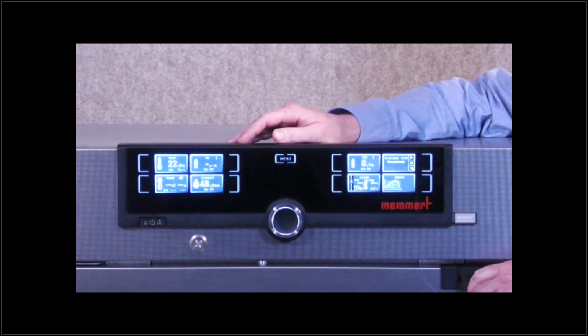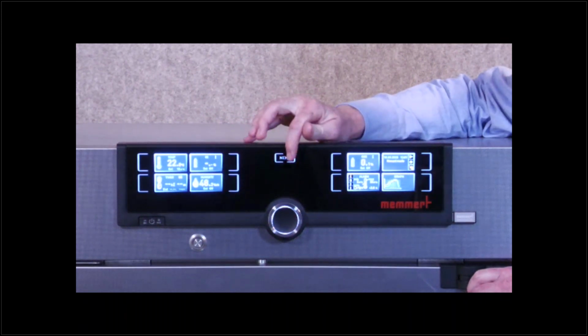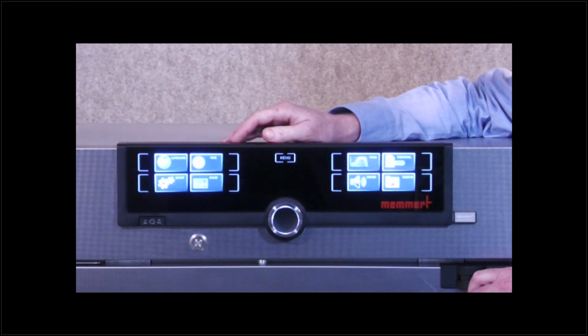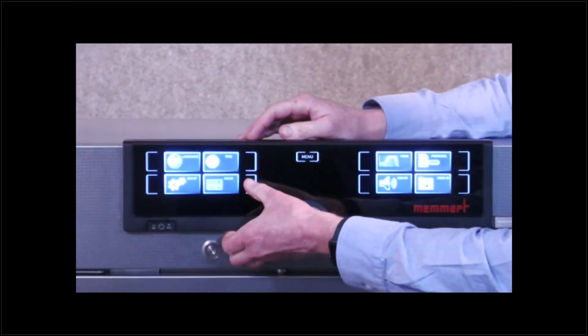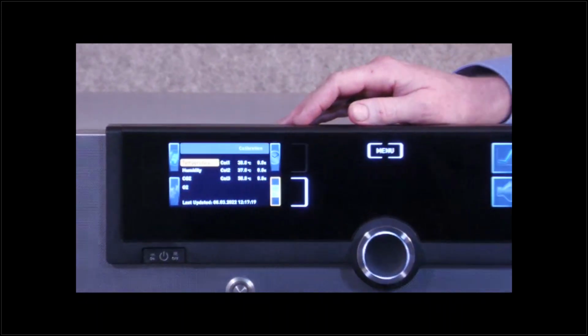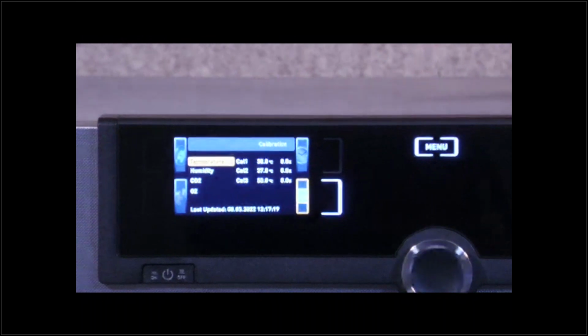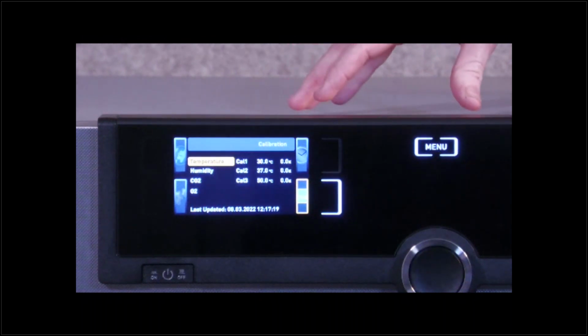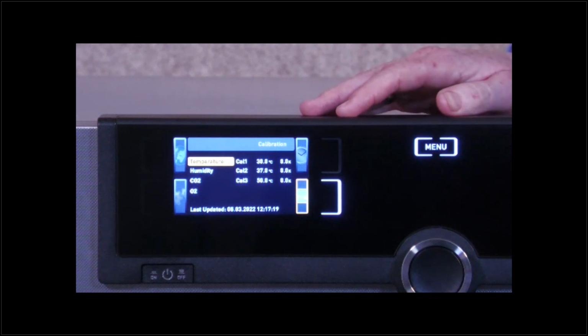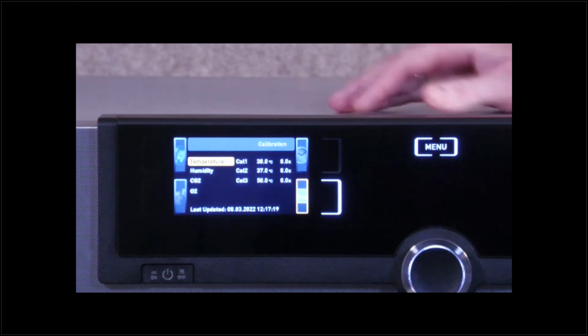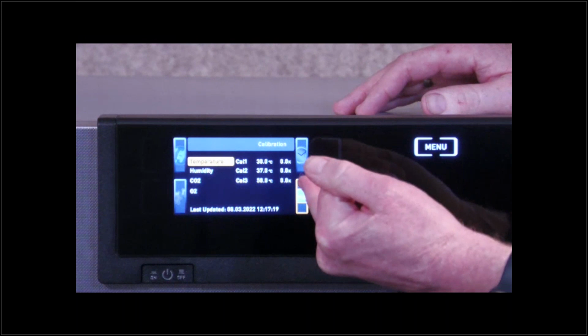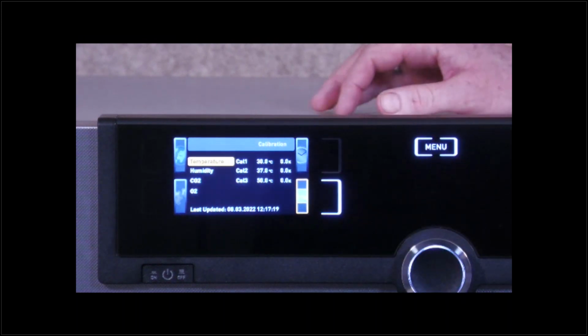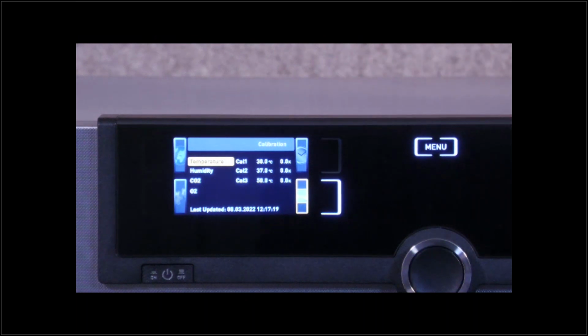At the end, we were talking about calibration. Here, I would also like to show you how easy it is with some units to do the calibration. If any difference between the reference sensor and the display temperature is observed during the calibration process, we can easily adjust these temperature differences directly on the controller. That makes it very easy to make sure that the appliance is always showing the right and correct temperature.